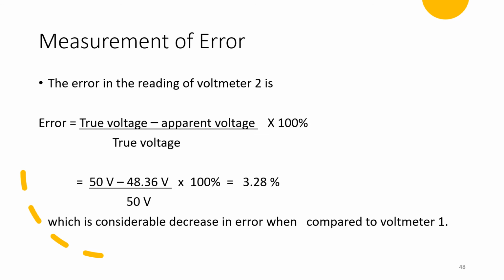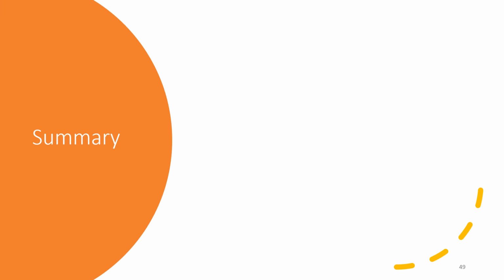Now for the second voltmeter: the true voltage is 50 volts, and the apparent voltage measured with the second voltmeter is 48.36 volts. Dividing by 50 volts into 100 gives a 3.28% error. So compared to the first voltmeter, the second voltmeter's error is only 3.28%.